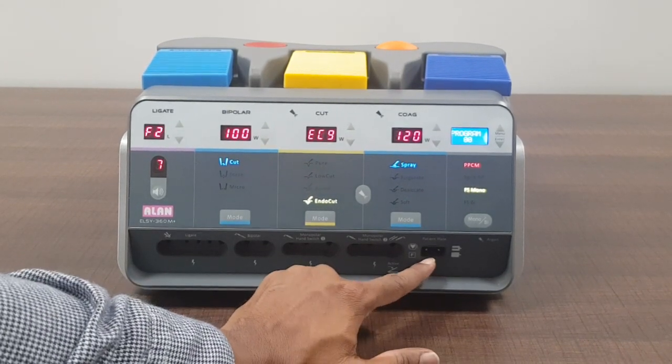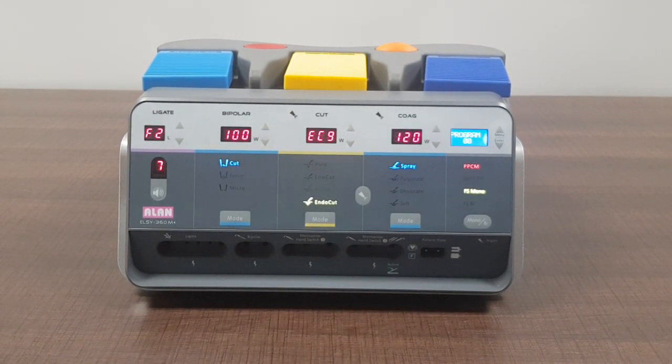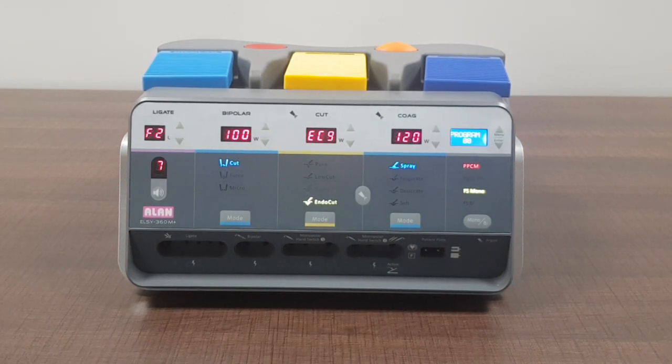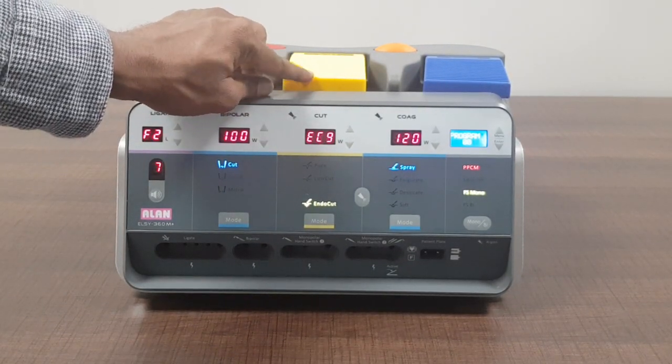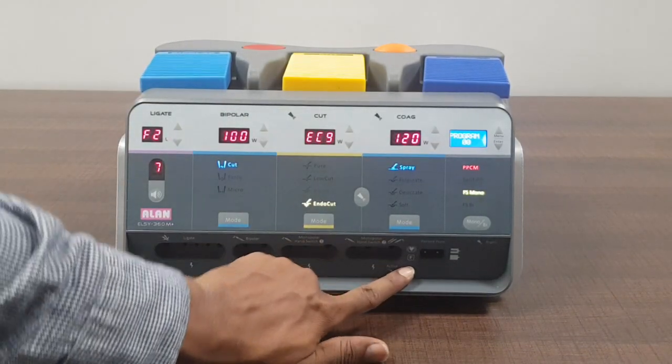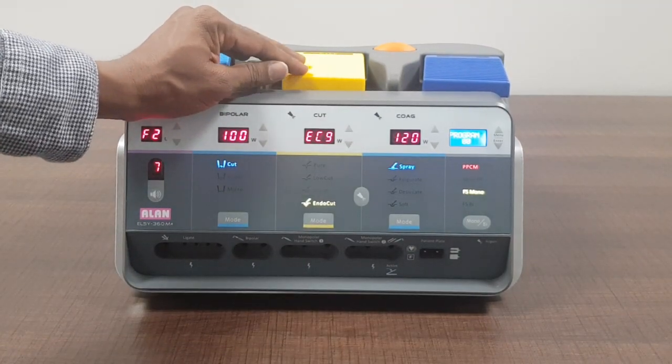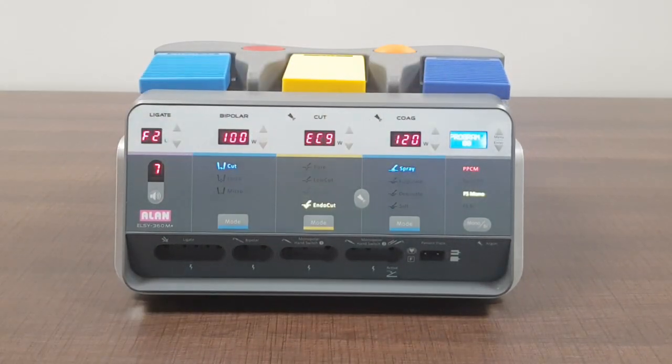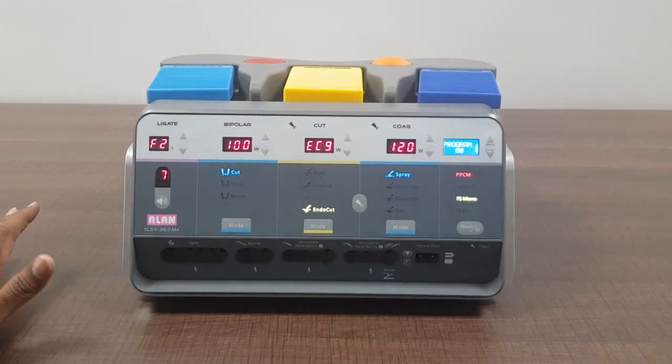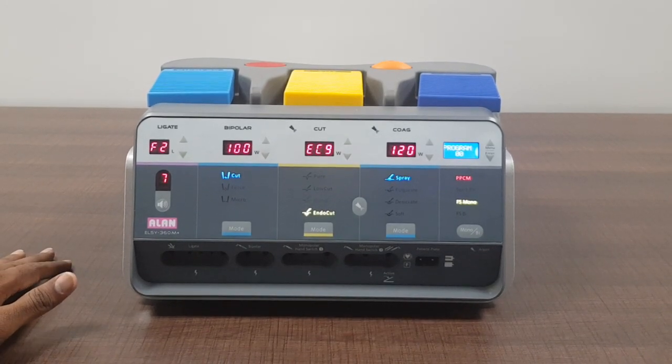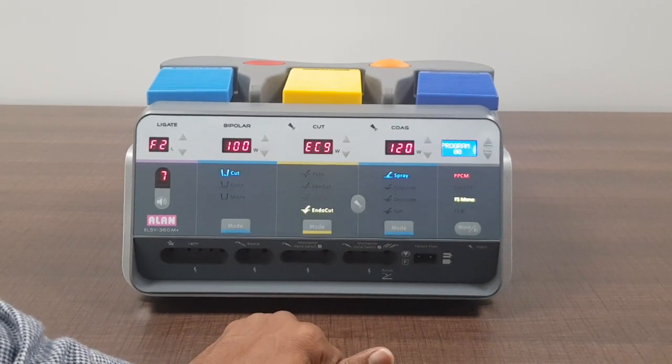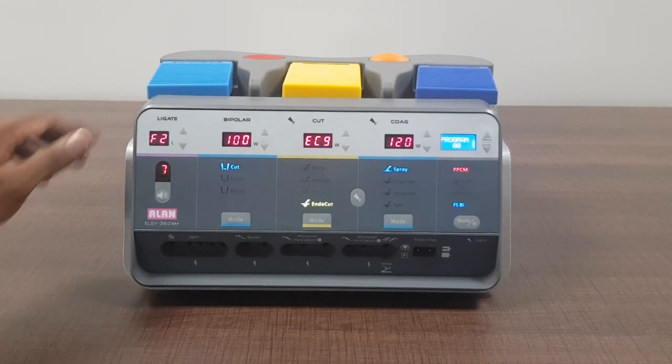I showed you two patient plates, one is the smaller one and the other one is quite bigger. As we work on concept called capacitive coupling and to show you on the other thing, this yellow pedal is used for monopolar cutting if you're using foot pedal. Right now we have not connected the patient plate so I'll just explain you in this way. This is for monopolar cut, this is for monopolar coagulation, and this is for bipolar. Now just like we spoke, when we want to use the golden tip then either we can switch it from here or from here or from here. Here it shows FS mono, that means foot switch is in monopolar, that is standard foot switch.